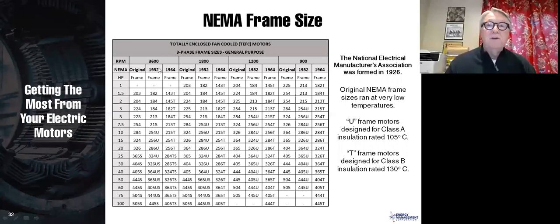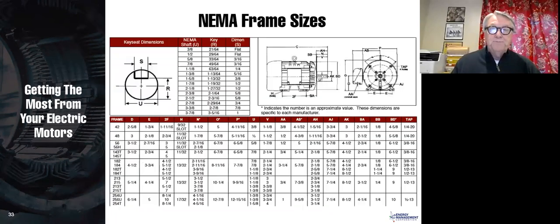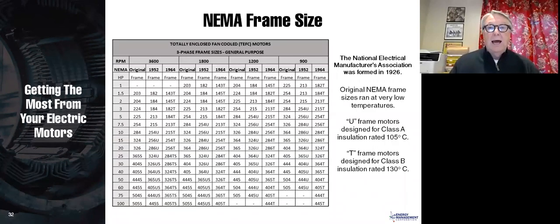In 1952, they redid the frame sizes, and they came out with what we call the U-frames. A lot of people still like those U-frames. U-frames allowed you to go with actually a smaller motor because we had better insulation available. But they were still 1952. We didn't have computers, so motors tended to be over-designed, and of course that's one of the reasons that people like them.